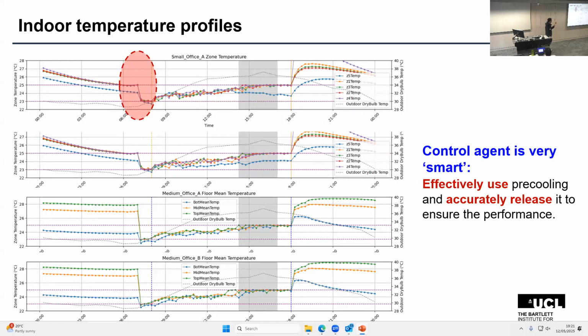This problem is challenging because if we have a higher temperature, we can minimize energy use, since higher temperature means lower cooling demand. But the problem is that with a higher temperature, the cooling stored in thermal mass will be over-released, meaning the cooling supplemented in the green zone, which is the peak demand event, will be insufficient. But if you have a lower temperature, you'll have higher energy use, but the cooling stored in building thermal mass will be over-sufficient for your peak demand limiting. So you need to find a proper level of temperature set point in this case.